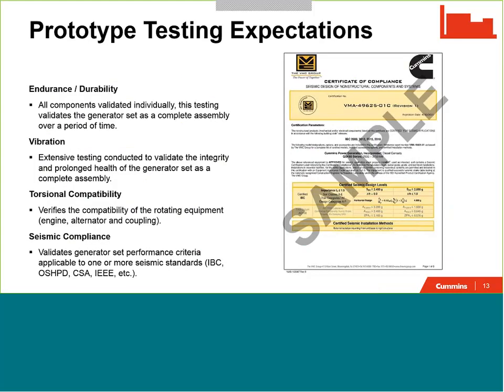What I'm going to move into and talk about next are the things that aren't specifically called out here and why they're important and why you should be calling them out in your specifications above and beyond what's listed here in NFPA 110. So, a few key components that I'll talk about. One, endurance and durability. All the products that are assembled by a generator set manufacturer have typically been tested by their respective manufacturers. However, not all generator set manufacturers test the product as a complete assembled unit, and it's critical that this be done.